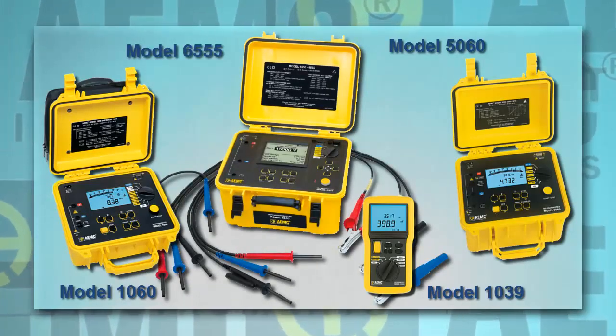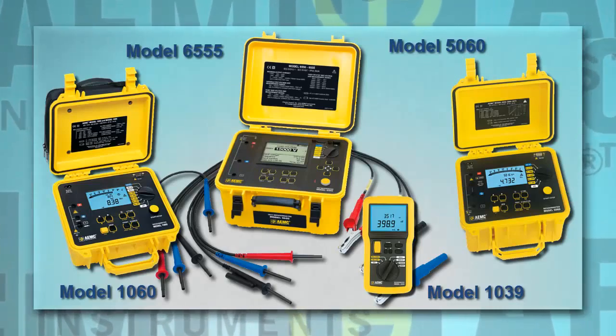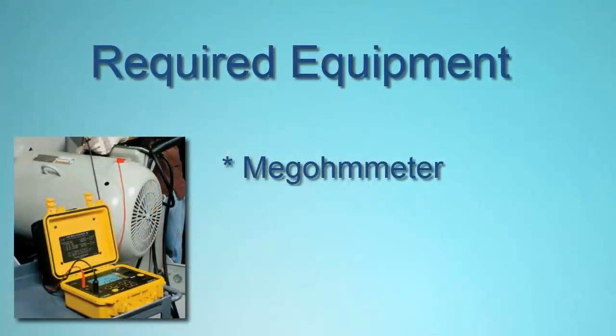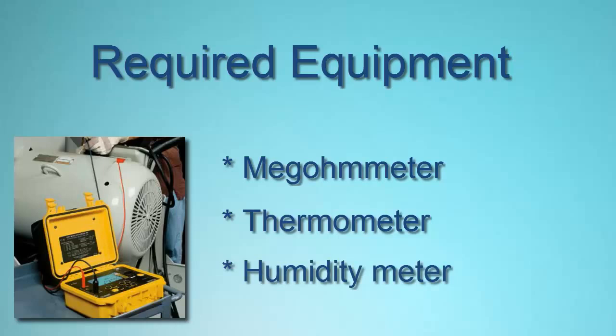And with some models, you can download and analyze the results on a computer running AEMC's DataView software. You will also need a thermometer or similar temperature measuring instrument. And if the equipment temperature is below the dew point, a humidity measuring instrument will also be necessary, especially when performing a spot test.